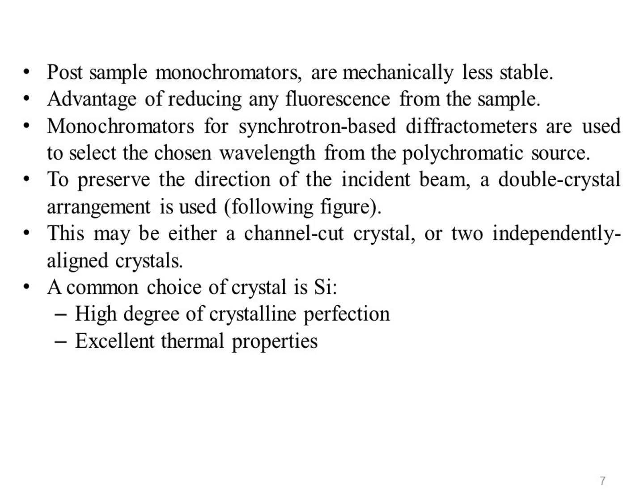Monochromators for synchrotron-based diffractometers are used to select the chosen wavelength from the polychromatic source. To preserve the direction of the incident beam, a double crystal, double bounce arrangement is used, as shown in the following figure. This may be either a channel-cut crystal or two independently aligned crystals.